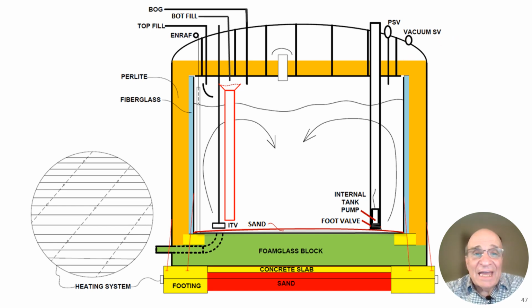Now, before that ever happens, what's not shown here is there is cover gas, which is a gas line that goes to your tank that would feed gas into the tank before you see a vacuum, but at very low pressures. So let's say a tank normally operates at 1 psi and you get down to 0.1 psi. Well, that cover gas would come in and supplement your gas. If the pressure still goes down and you see a very slight negative pressure, this vacuum safety valve would open.